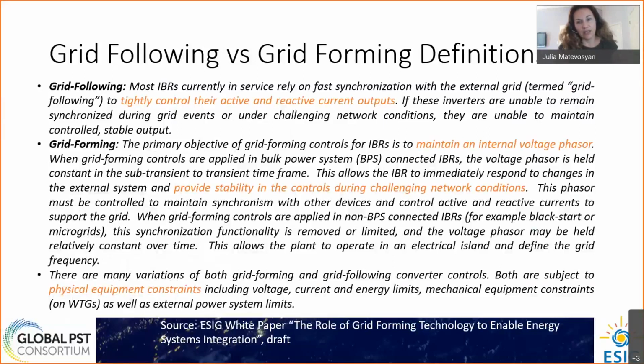Just to set the stage, let me explain what we mean by grid following and grid forming definitions. I pulled up the definition from the white paper. Grid following are the inverters that we mainly have on the grid today. They rely on fast synchronization with the external grid to tightly control the active and reactive current outputs. If these inverters are unable to remain synchronized with the grid, or under challenging system conditions, they are unable to sustain controlled and stable output.